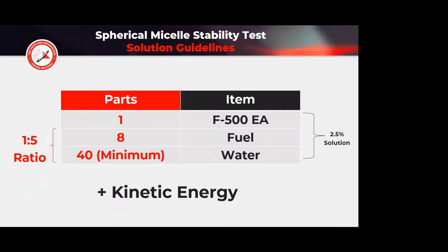We have a specific encapsulation ratio that is used to accomplish the encapsulation, which takes 1 part of F500 encapsulator agent, 8 parts fuel, and 40 parts minimum of water. I'll get back to the minimum. And then kinetic energy, some sort of agitation, usually provided by just the nozzle stream or the sprinkler stream going on to the fire. If we look at this ratio here of 1 part of F500 to 40 parts of water, we end up with a 1 over 40 is 2.5%. So technically, we can encapsulate with the 2.5% solution, but since most existing fire equipment is 3%, we just dial our Class B up to a 3% mixture.